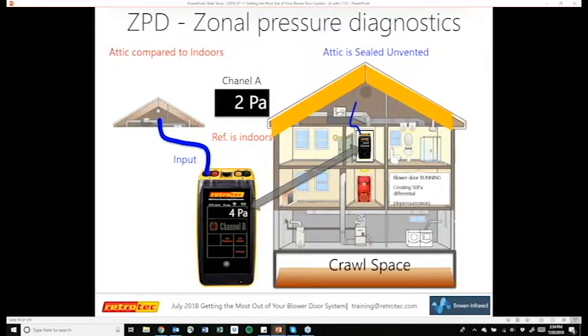For a sealed attic, if you have spray foam, this is a good way to see if that spray foam on the roof deck is really working the way it's supposed to prevent infiltration. So if you do the same thing, you would have the attic hatch closed. If it's reading about the same, close to 0, so if you get 2 instead of 0, that's really close. That means that spray foam is doing a really good job.